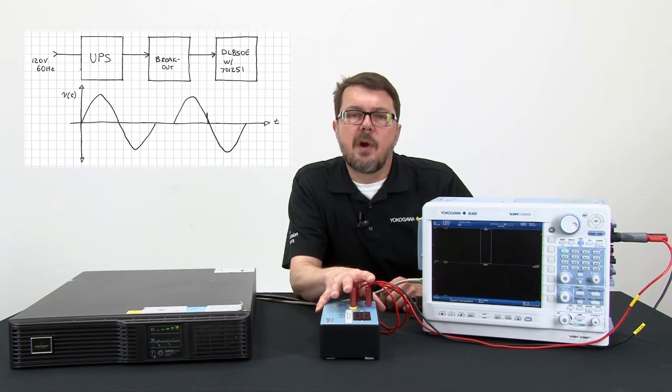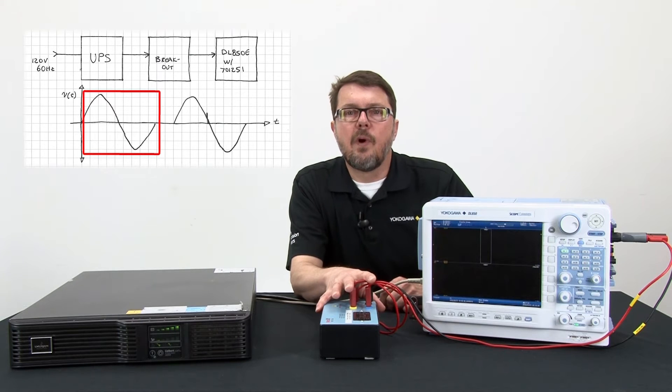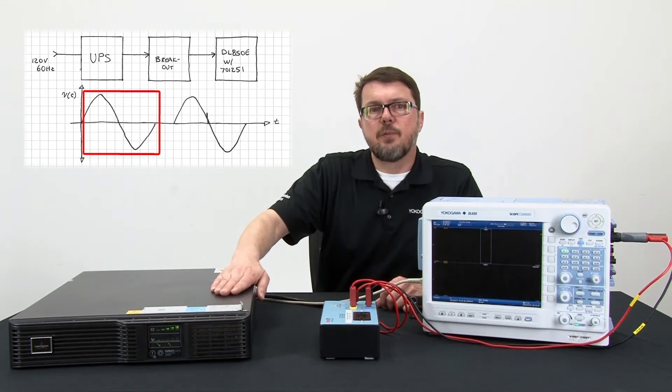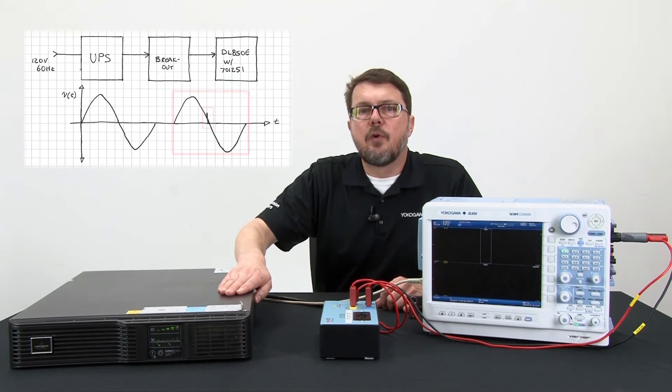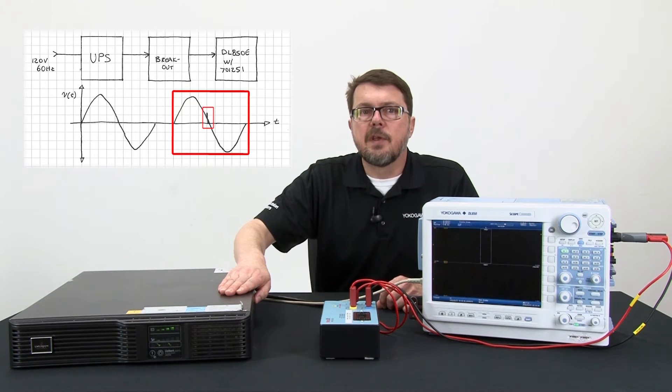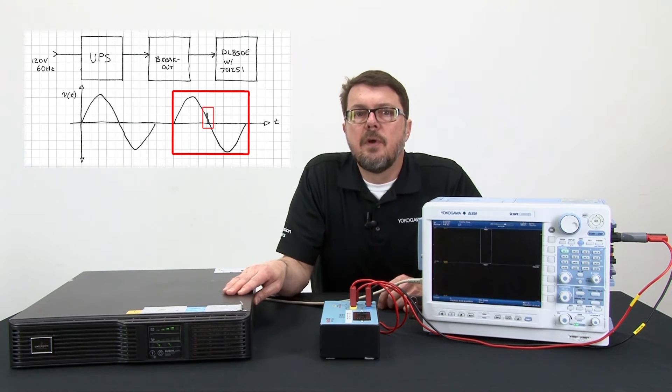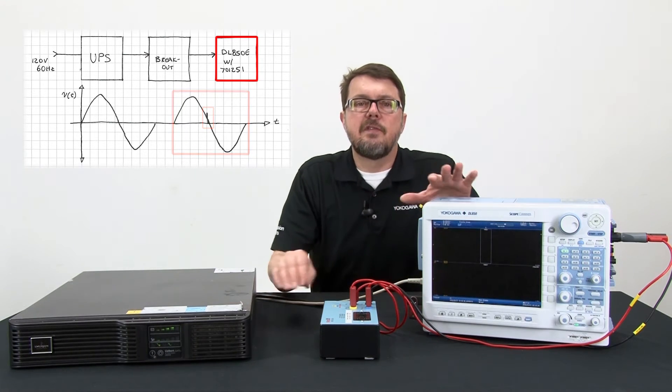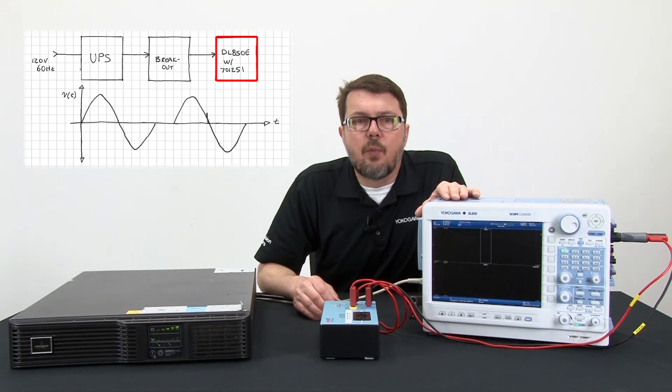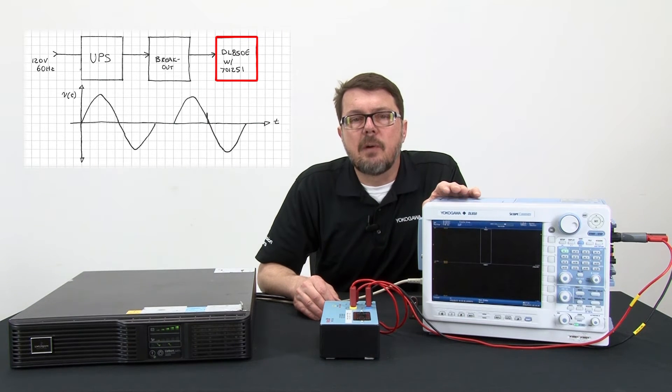I'm set up so that I can monitor the UPS voltage waveform while I force the UPS to switch from mains power to inverter battery output. There will be a very small glitch or anomaly on that AC waveform when that switchover occurs, and I want to catch and view that on the DL850 scopecorder. To do that, I'm going to use the wave window trigger, a standard trigger option on the DL850E.